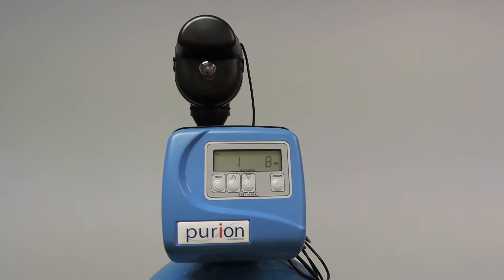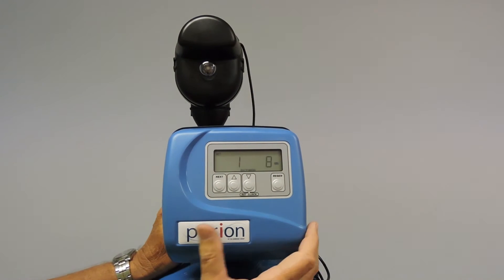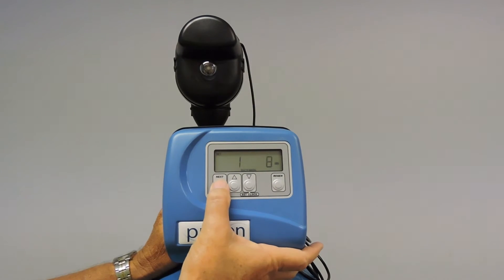Now we're up to our cycle times. This is where we put all our timing for each cycle through the regeneration. We start off with a backwash. Eight minutes is our generic time that we use for the softeners. So we'll accept that.